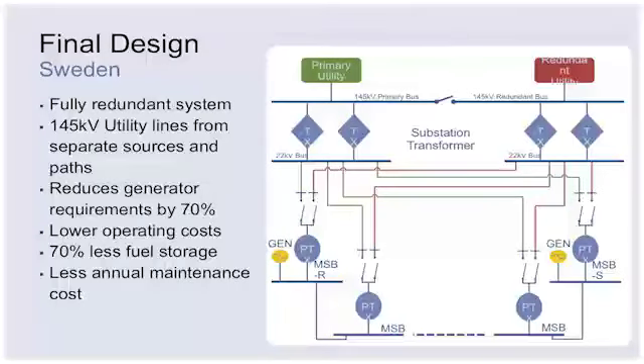We were able to reduce our generator footprint by 70%, which translates into significant cost savings on capital, and also negates the need to truck a lot of fuel to the site. The reason for the generators is really just to keep the network equipment warm while we fail the region over, in the event that we've lost both substations, to one of our other regions globally.